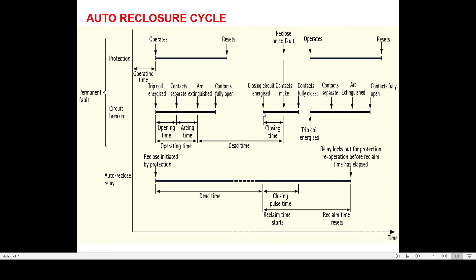Once the contact is in fully open condition, if the autoreclosure relay has a dead time of one second, then after one second — which is the dead time — it will issue a closing command to the circuit breaker. The dead time of the autoreclosure relay starts from the moment the autoreclosure relay receives the AR start signal from the distance protection relay. After the dead time lapses, a closing command is issued, the closing coil energizes, and after the closing time the circuit breaker closes. Once the arcing contacts and main contacts are both properly closed, the circuit breaker will be in the closed condition. The reclaim time then starts from the moment of this circuit breaker close.